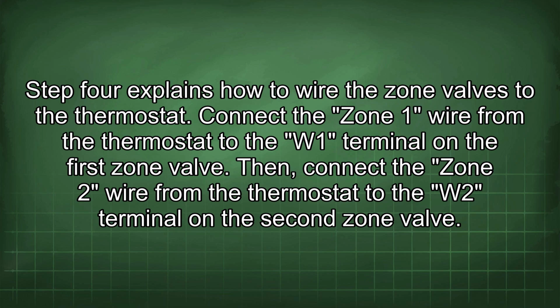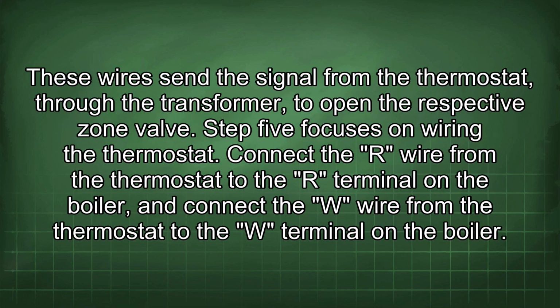Step 4 explains how to wire the zone valves to the thermostat. Connect the zone 1 wire from the thermostat to the W1 terminal on the first zone valve. Then connect the zone 2 wire from the thermostat to the W2 terminal on the second zone valve. These wires send the signal from the thermostat through the transformer to open the respective zone valve.